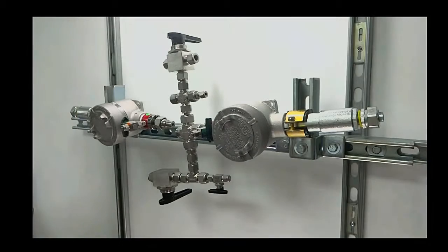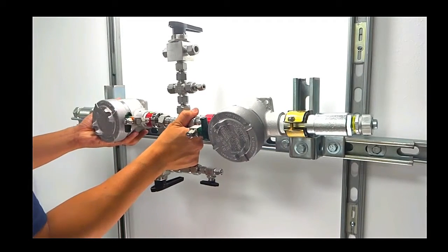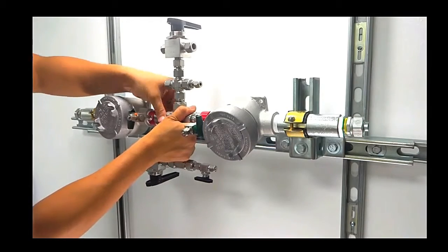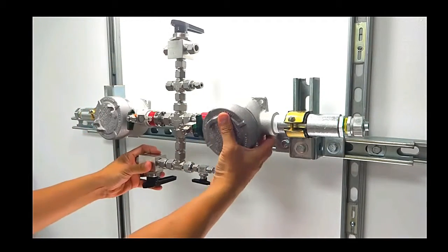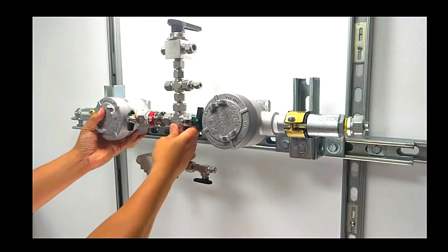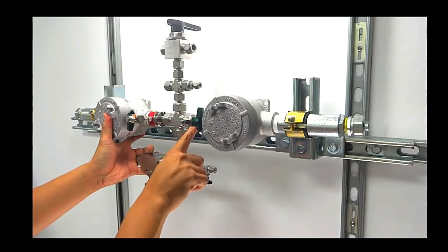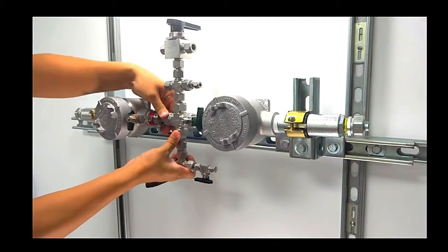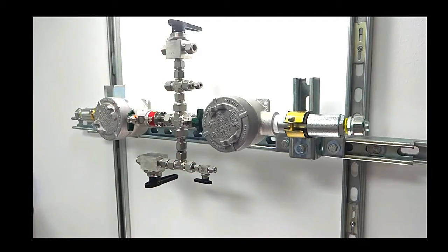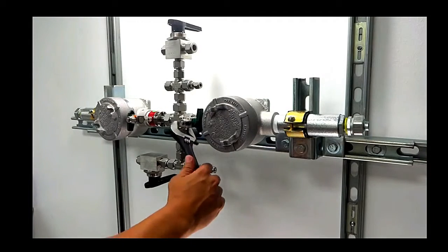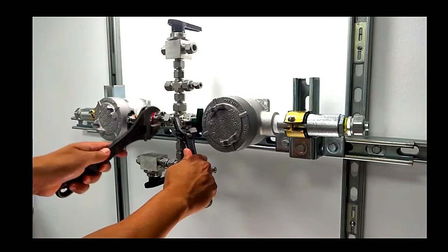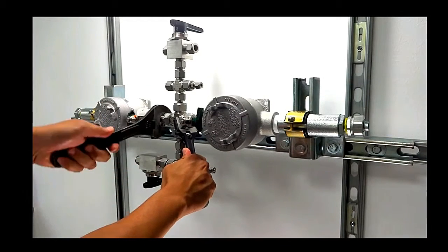Step 7. Reassemble and realign. In order to avoid cross-threading, nuts should be tightened first by hand. Ensure that your alignment marks that you created in Step 2 are realigned in the process. Once again, tighten nuts by hand. Step 8. Tighten probe fittings. Tighten down to full seat, plus 1/4 turn.